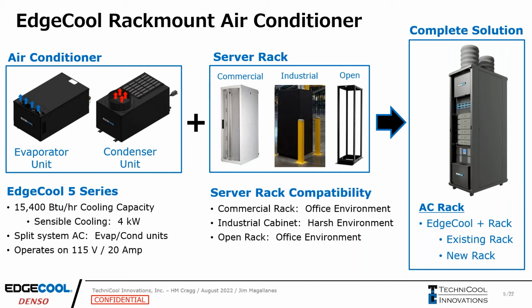And it works with any type of rack, whether it's a commercial datacom rack where you have the perforated front and back doors, industrial server racks where it's NEMA rated to keep out dust and water, or an open rack, helping with the maintenance on the IT network or the VoIP, the telecommunications equipment inside. So what happens is you combine the air conditioner and the server rack, and that's the complete solution. And again, we're being installed into new racks or existing racks. And that's kind of what set us apart from Uptime Racks, where the Uptime Racks air conditioned server racks that we produce are just for new racks. And this is allowing us to go into existing racks, which opened up a whole new market for us.